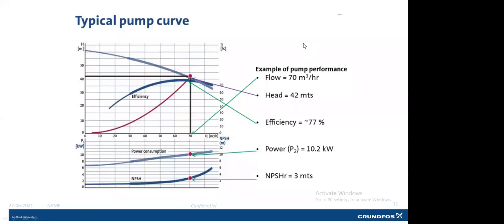Thank you, sir. And then there's the next question: how to calculate or know the pump head of a running pump? We can check it by installing pressure gauges at the pump suction as well as the discharge. And head is nothing but the differential pressure across the pump. So at discharge, if the pressure is 4 bar, and at suction it is 2 bar, the differential pressure is 2 bar. So the actual head would be 20 meters of water column.